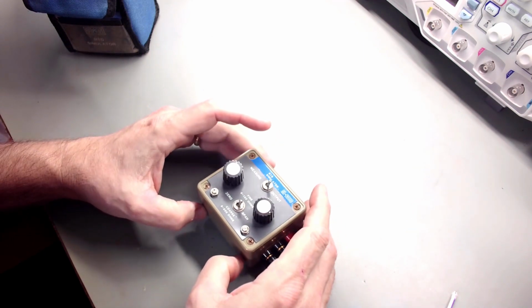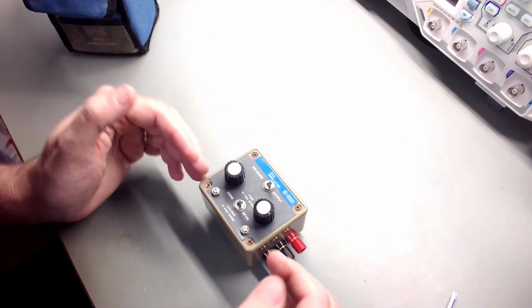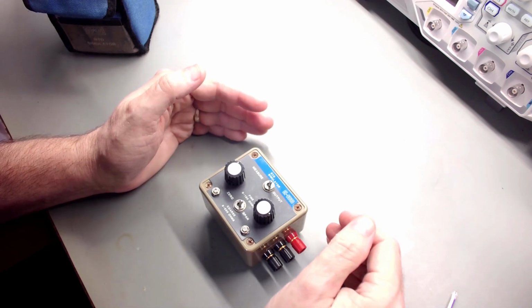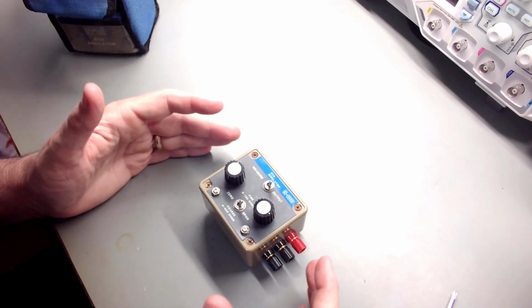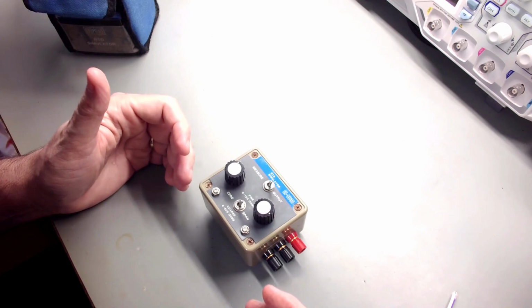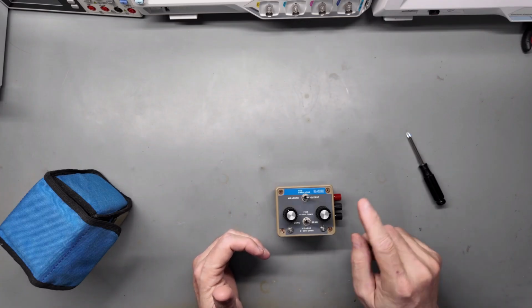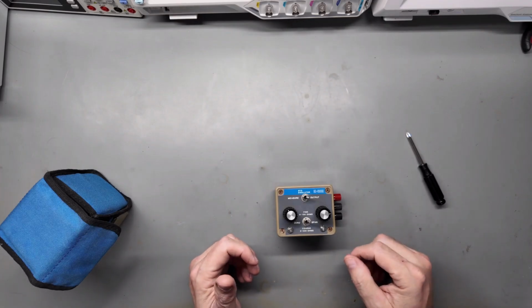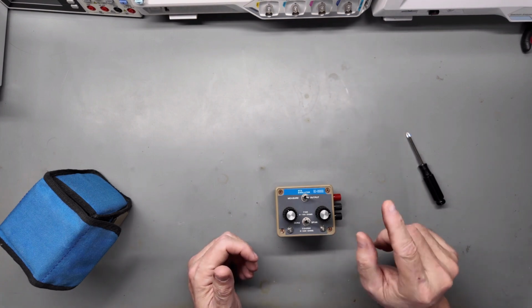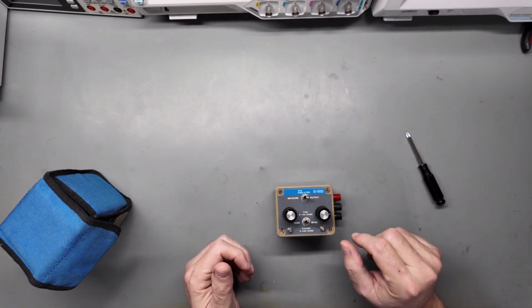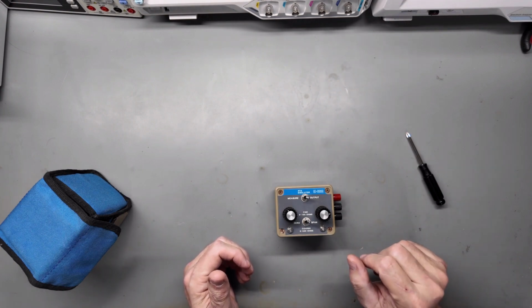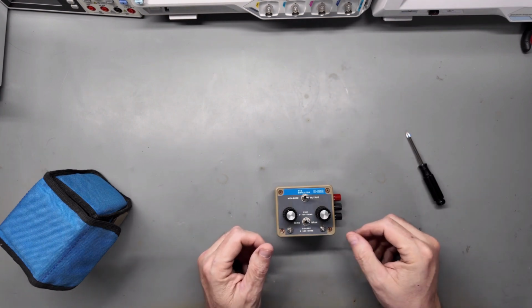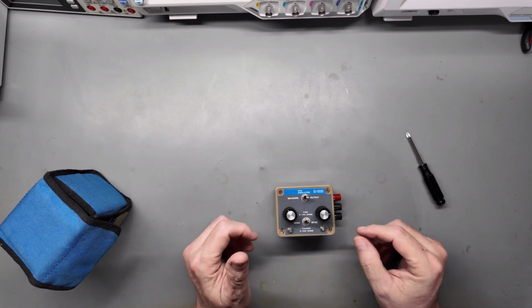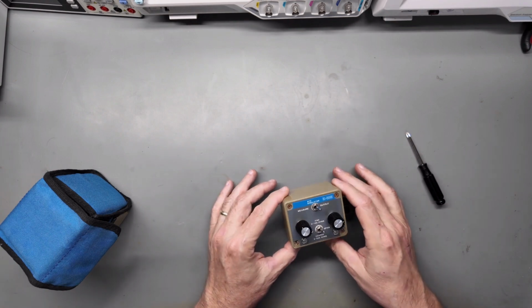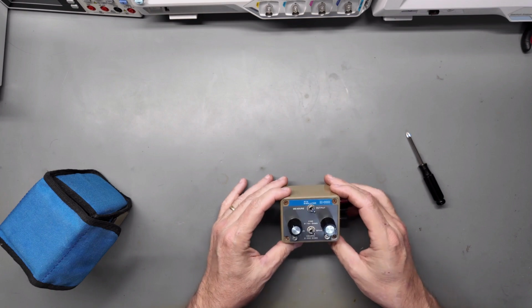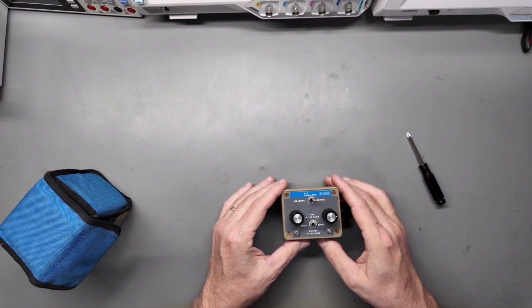So there were these types of devices, and they went up in levels and sophistication. They made ones that were like handheld signal generators. Basically, you plug in a temperature and it would generate the right resistance. You could tell it what type of thermocouple or resistive temperature device you were using, then tell it what temperature you wanted to simulate, and it put out the right resistance signal. This one was simpler. Now, even though they were simple, they weren't cheap. These things were over $1,000 in their day.